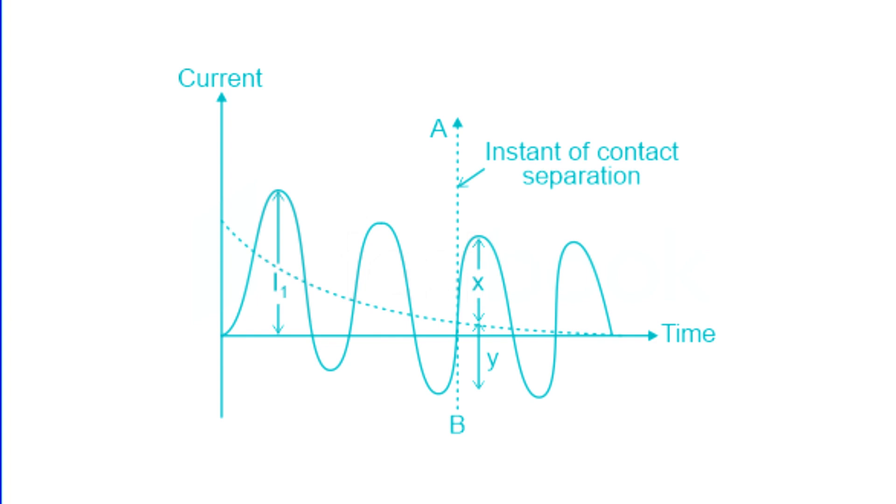Consequently, the making current must be higher than the breaking current. If the symmetrical breaking current is known, the making current can be determined. Let the symmetrical breaking current be I, then the peak value of the symmetrical breaking current will be root 2 times I.